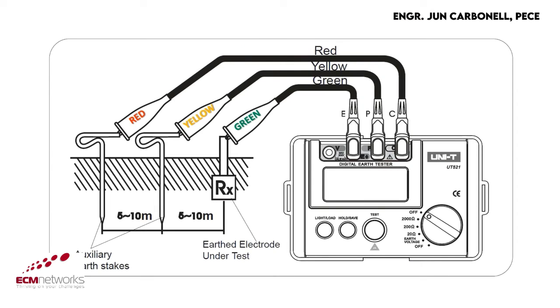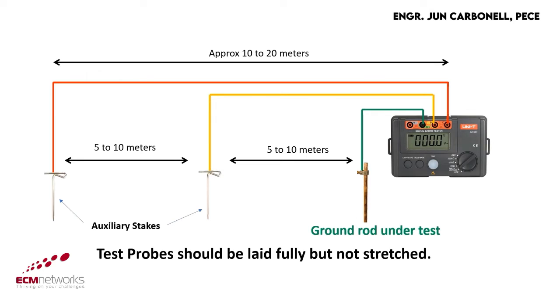On earth testing, connect the 20-meter red test lead to the C port, the 10-meter yellow test lead to the P port, and the 5-meter green test lead to the E port or the green port. The red test lead should be clipped to the auxiliary stake located at the farthest point of at least 10 to 20 meters away from the tested ground rod.